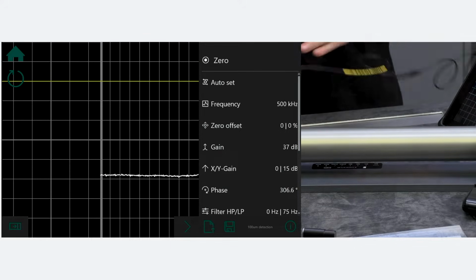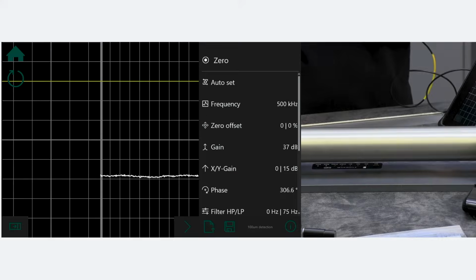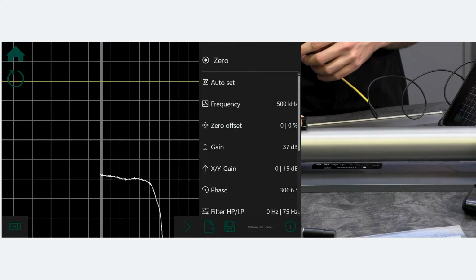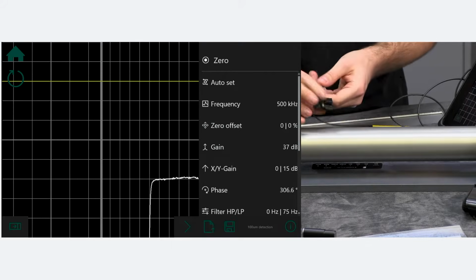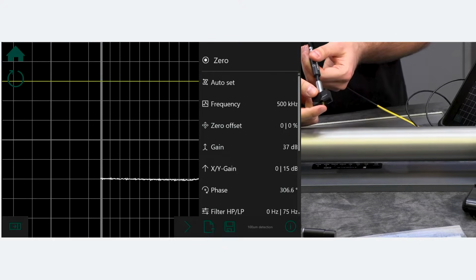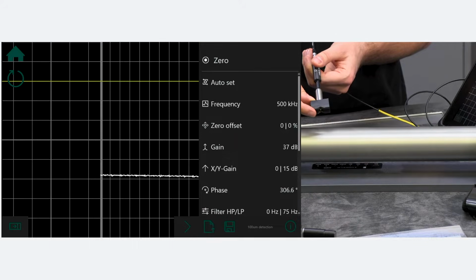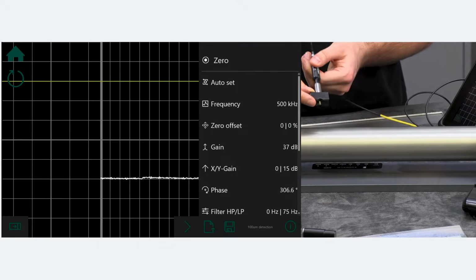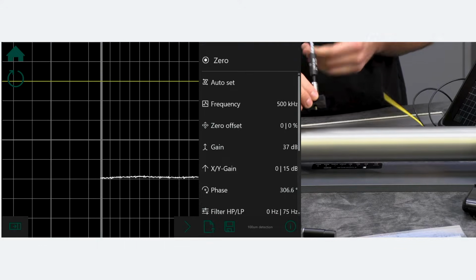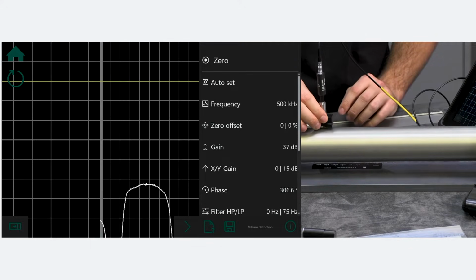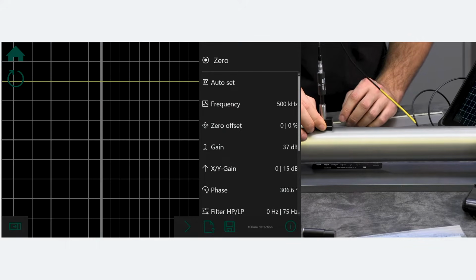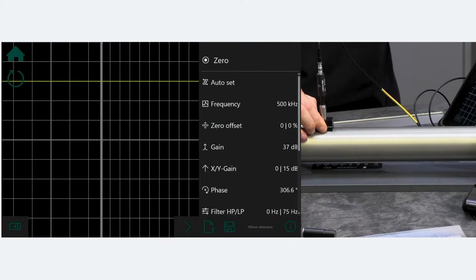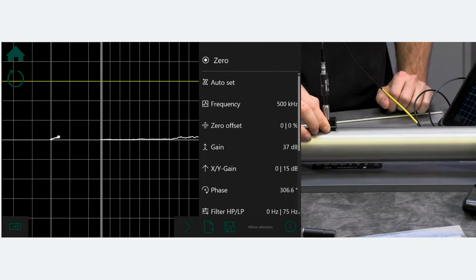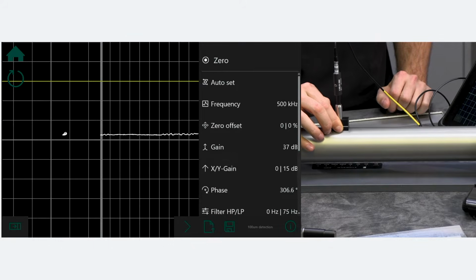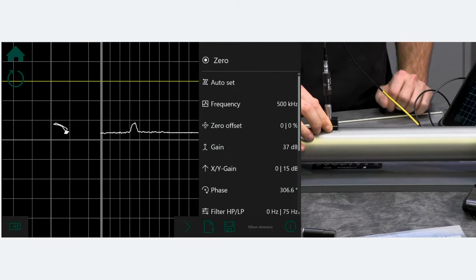And there we are. It's already running. I can put the probe on the material. You see here, it's really a standard pencil probe and a guidance with the spring loaded. So it's mounted here, and we have a constant pressure with the probe on the material, and I'm very good at scanning. So I make 0 on the material, and we can start scanning, and there we see the crack comes really nicely as a signal.